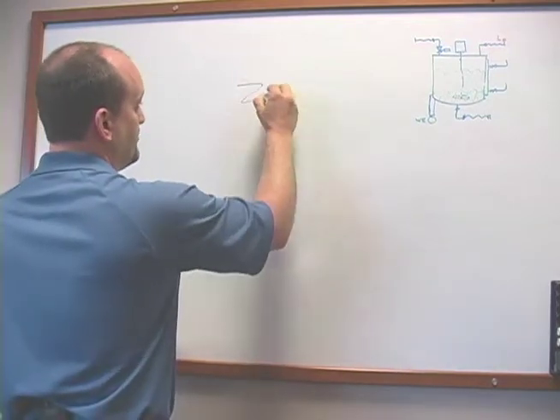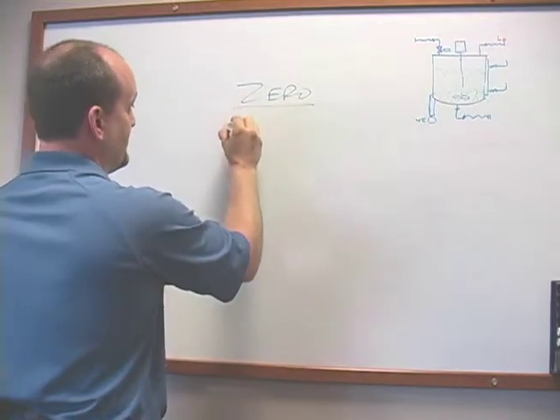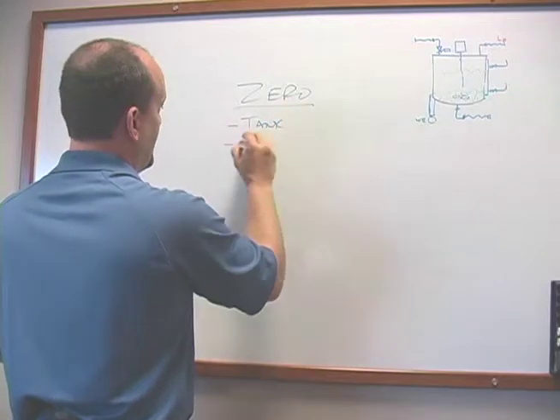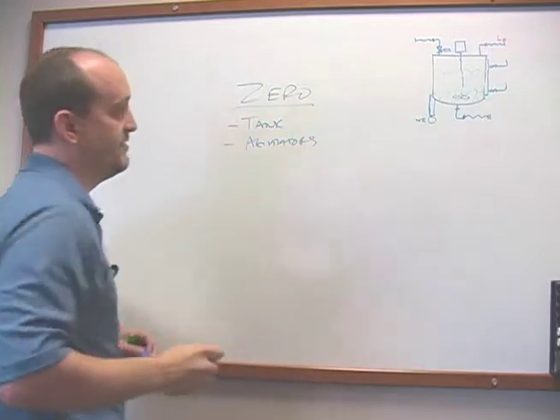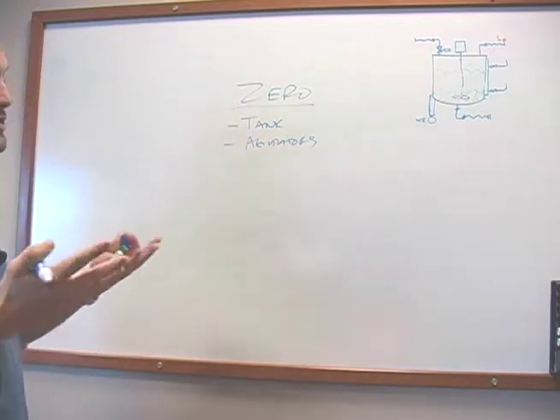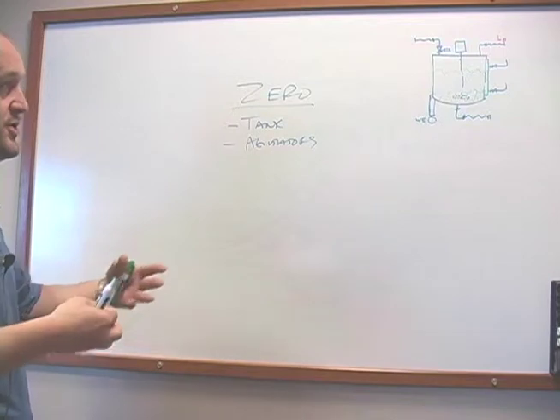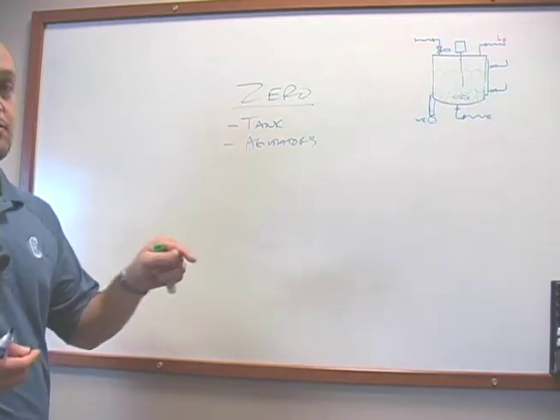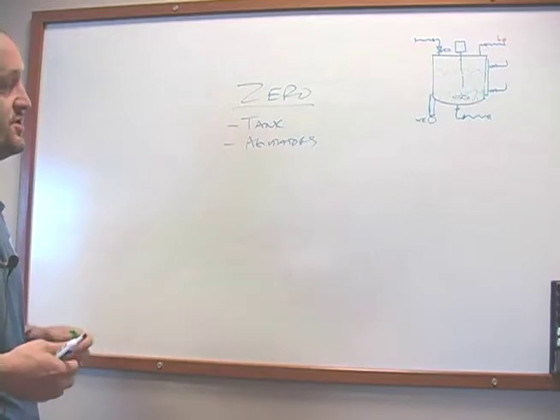So when we zero, you're negating your tank and agitators and anything else that you don't want to measure. So once all that stuff's on there, there's no fluid in the tank. Your load cell measures 2,000 pounds. You hit zero. It's just like taring out a scale in a shipping department. That's what zero is.